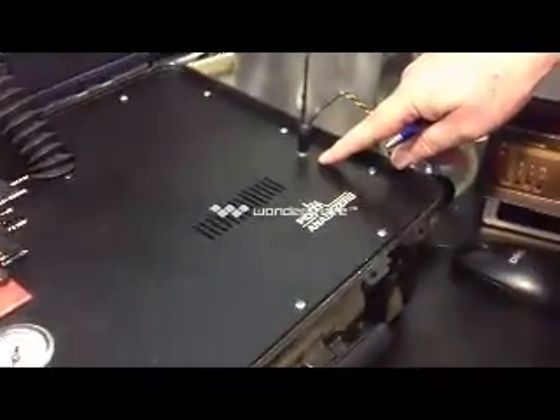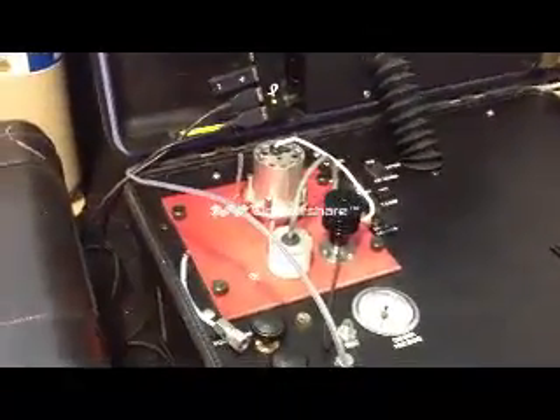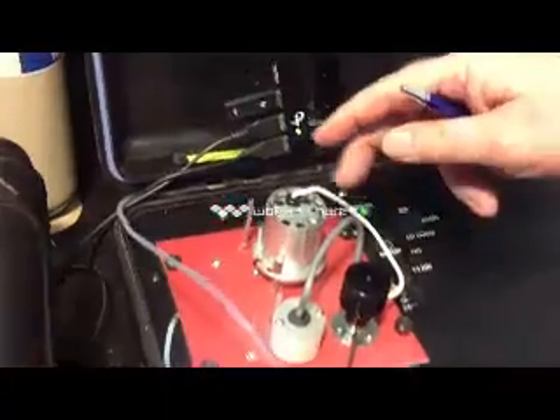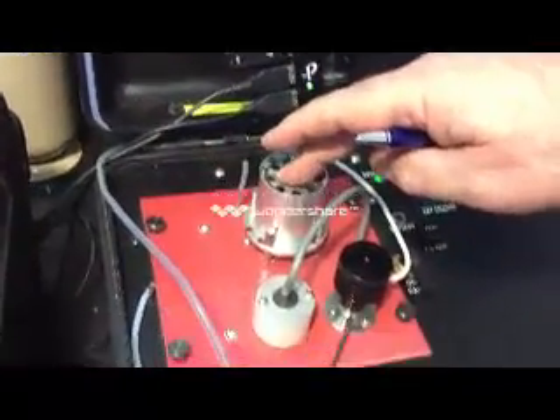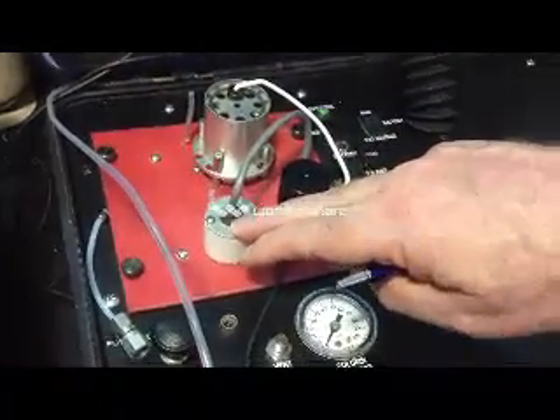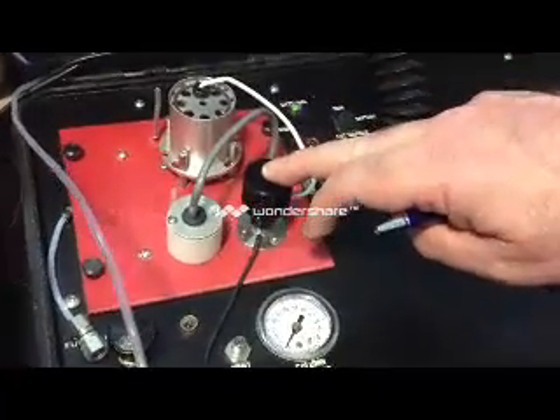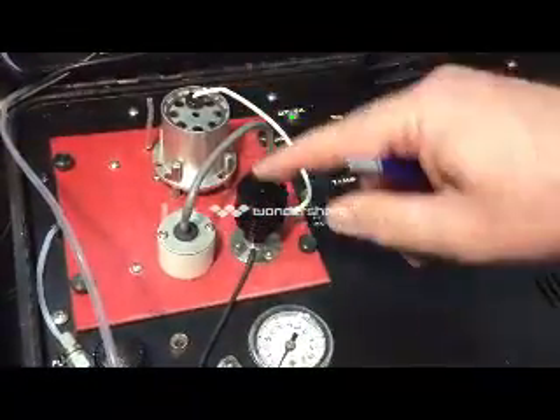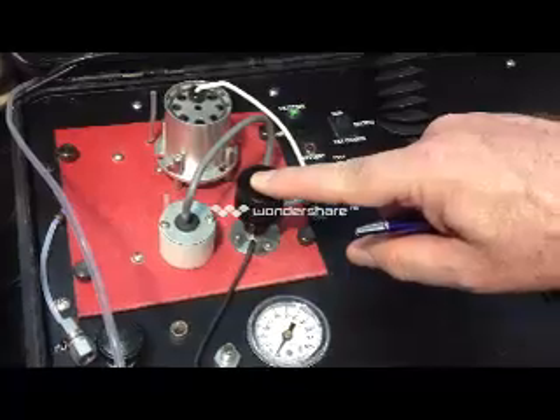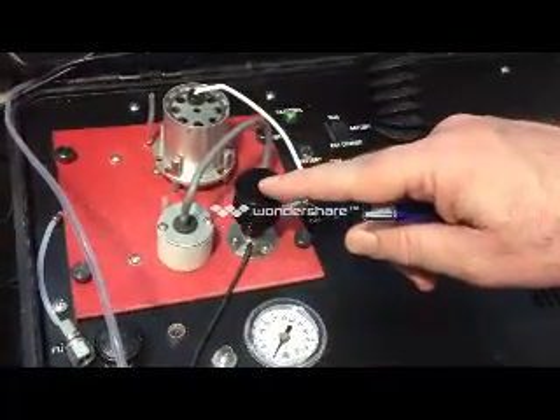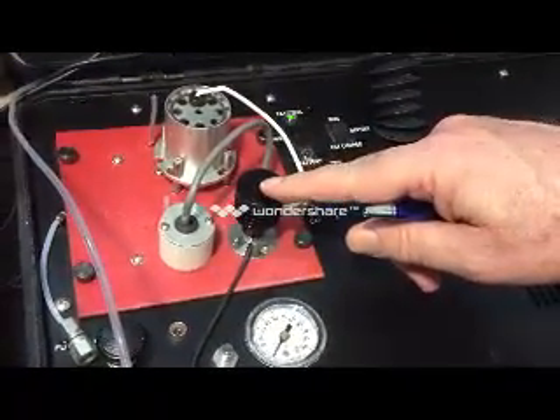This particular instrument is a dual column instrument for doing mining gases, and basically this is a far UV detector, this is a thermal conductivity detector, this is the gas syringe injector. There's also a 10-port valve that's used to inject the sample.